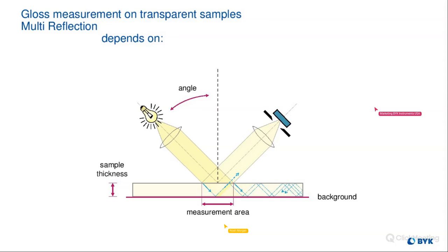If you find that it's become opaque due to the color properties of it, you might be able to get away with not using a background because the light isn't able to penetrate through the color of that film. So, you really can't go wrong with using a background, because either way, if the light's able to pass through or not, it won't play a role in that measurement. So, when in doubt, using a matte black background is a good way to start out. Yeah, good advice. Good advice.